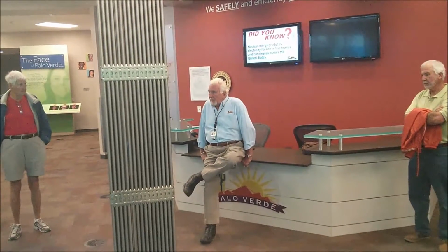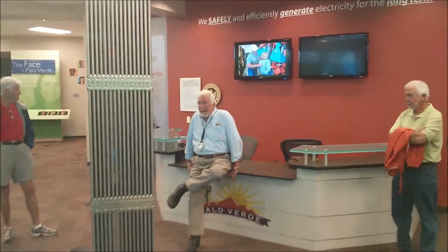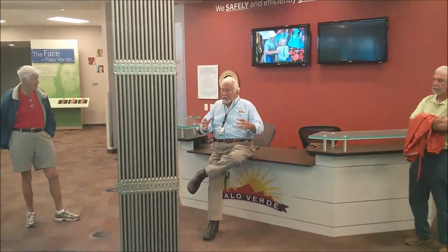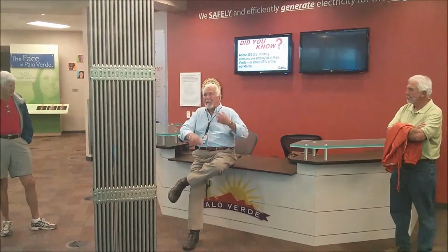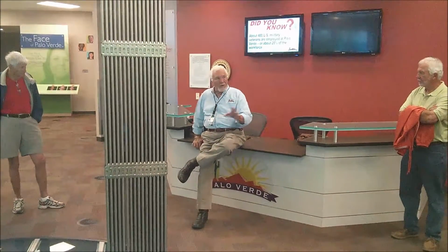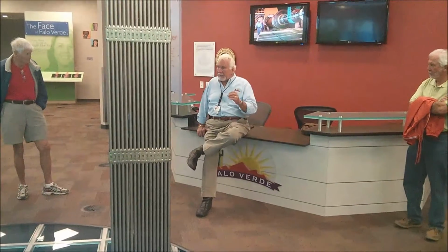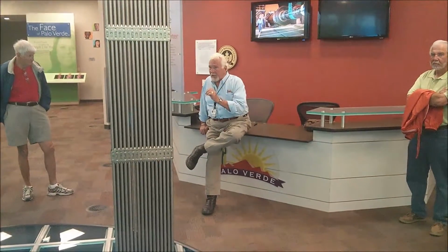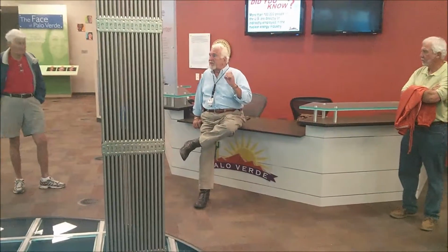Yeah, see, that's not the problem. Shutting down's not the problem. Keeping it cool after it's shut down is. And that doesn't have anything to do with the grid. That has to do with electrical systems we have right there at Palo Verde to provide electricity to keep pumps running to circulate water. Once we start the nuclear reaction in the fuel, we can shut down the nuclear reaction in a second. What we cannot shut down is what we call decay heat, and I'll explain exactly where that comes from. But a good analogy or a good similar comparison is if you think of an electric stovetop.